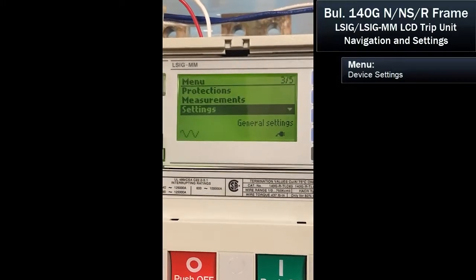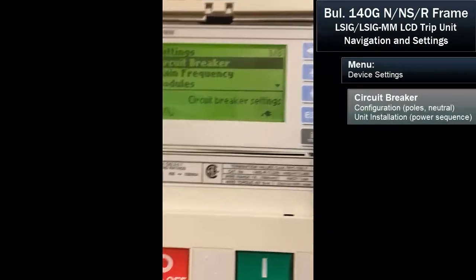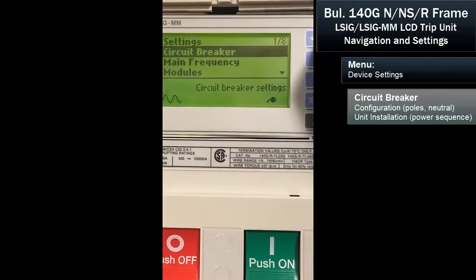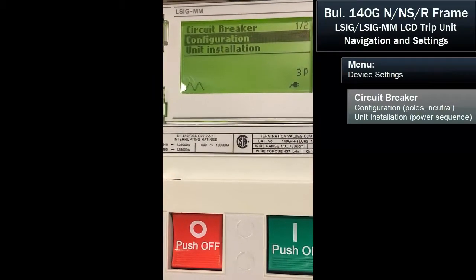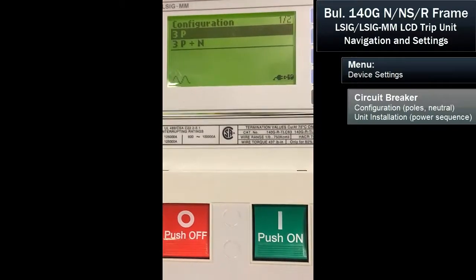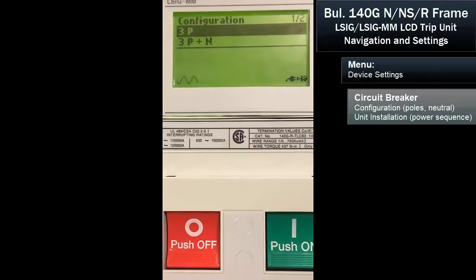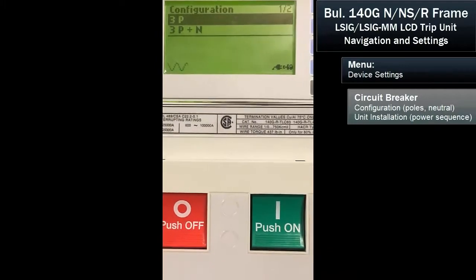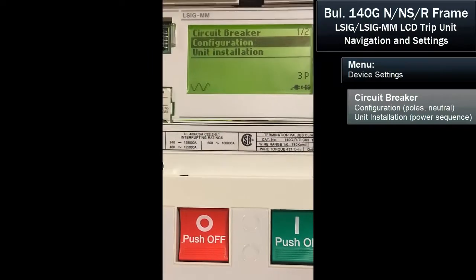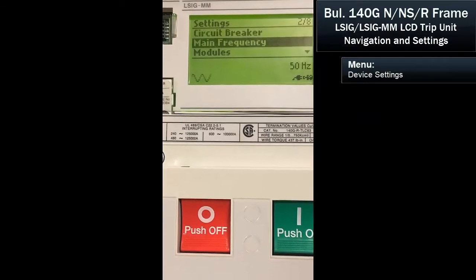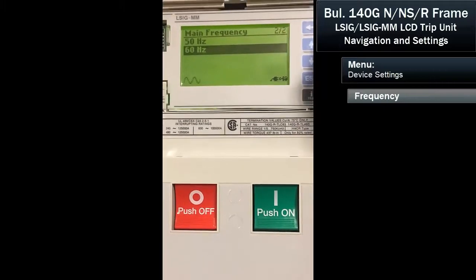The next item is the breaker settings. There are eight settings. We can look at the circuit breaker configuration — it's going to set up the protections for how it's wired. In this case, it's a three-pole breaker, so our options are three pole or three pole plus neutral. This is a three pole. We can also set the protection frequency — being in the states, I'm going to set it for 60 hertz.